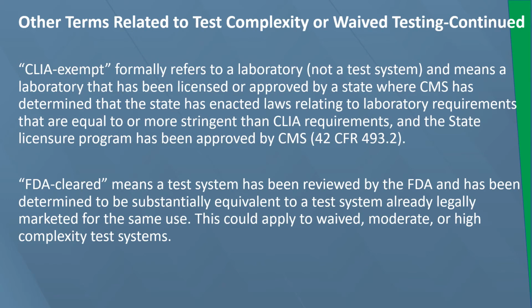FDA-cleared means a test system has been reviewed by the FDA and has been determined to be substantially equivalent to a test system already legally marketed for the same use. This could apply to waived, moderate, or high complexity test systems.